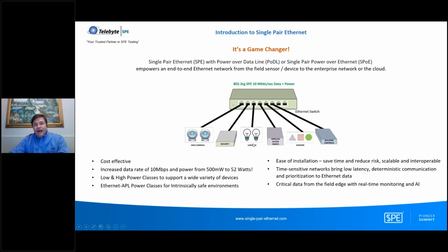So the applications that you could support over an Ethernet network with higher level software applications is really what the Internet of Things and Industry 4.0 is to drive. So what we're doing then over this 2-wire technology, 1 pair with data and power, we're increasing the data rate from the legacy 2-wire devices from kilobits per second up to 10 megabits per second. And that's full duplex, so transmit and receive simultaneously. And we're also supporting power over the same pair from 500 milliwatts low power to high power, 52 watts. So with the low and high power classes, we can support a wide variety of devices on the network.